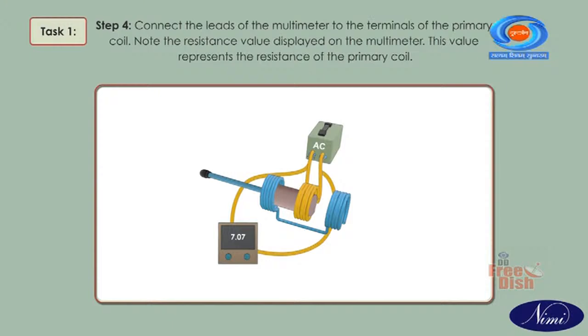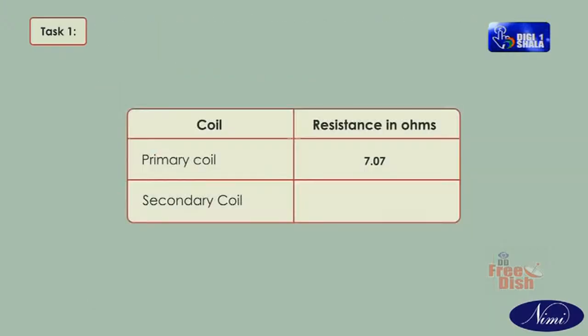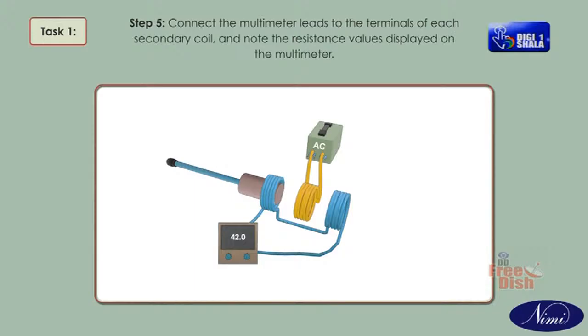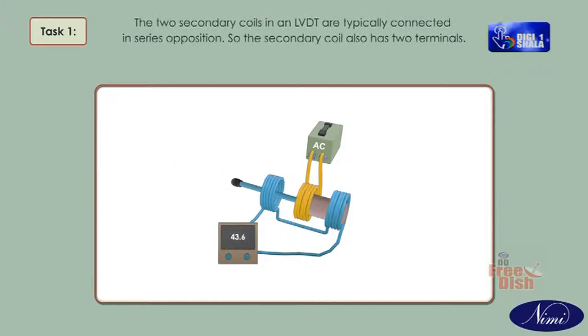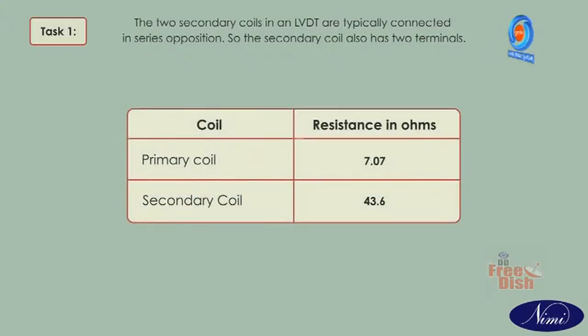Note the resistance value displayed on the multimeter. This value represents the resistance of the primary coil. Coil, primary coil, resistance in ohms, secondary coil. Step 5. Connect the multimeter leads to the terminals of each secondary coil and note the resistance values displayed on the multimeter. The 2 secondary coils in an LVDT are typically connected in series opposition. Coil, primary coil, resistance in ohms, secondary coil.